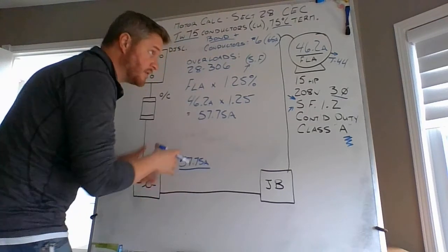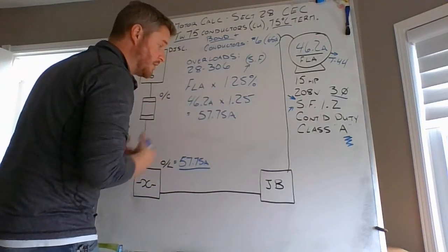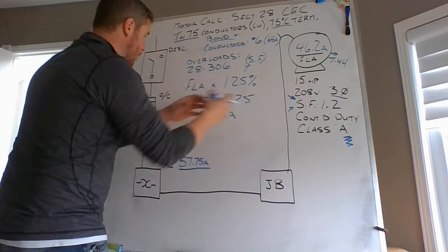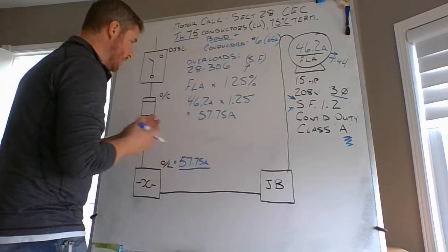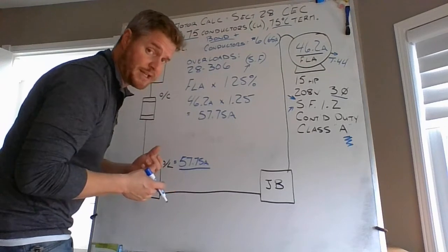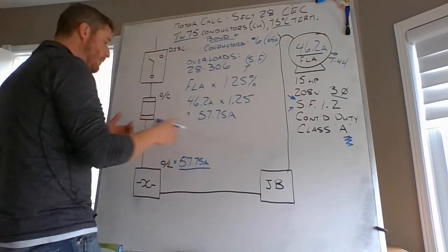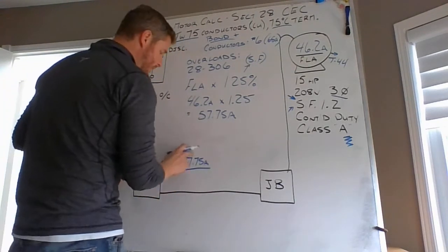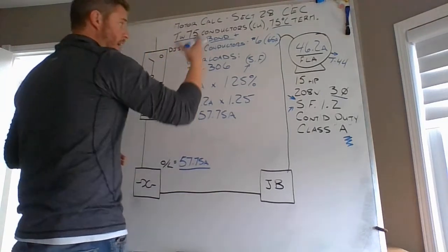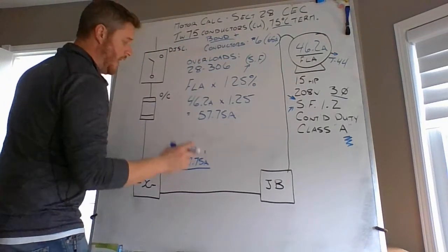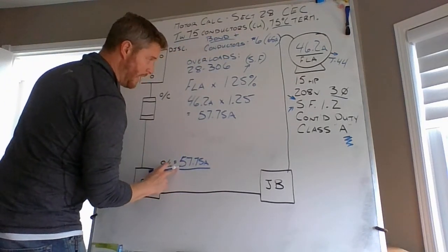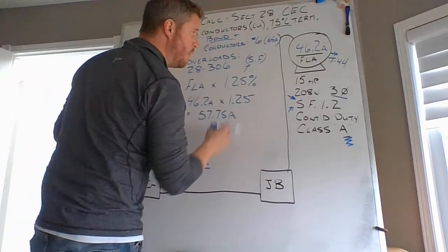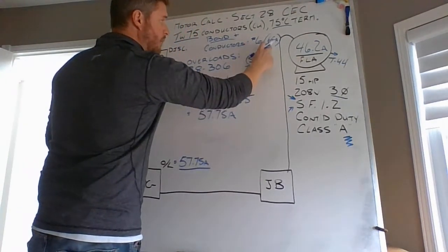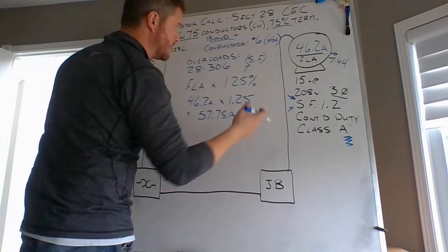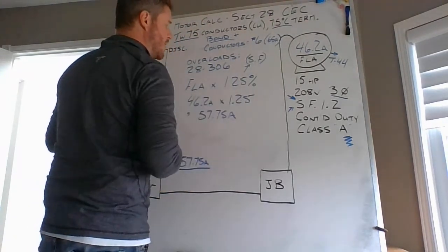There's two different sections within Section 28. It's two different rules, but it's the same multiplier. So be very careful of this in the future. This might save you a little bit of time. We've already calculated that 57.75 amps would be my conductor's minimum ampacity. I took my 57.75 amps and I went right to Table 2. I found that my number 6 at 75 degrees Celsius was good for 65 amps. That was my chosen value.